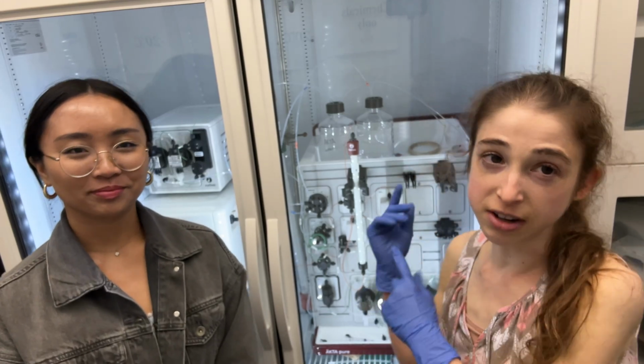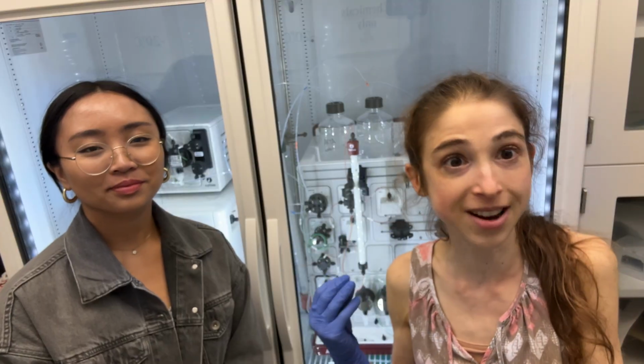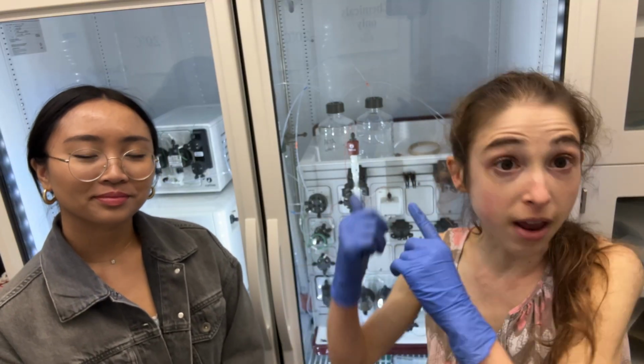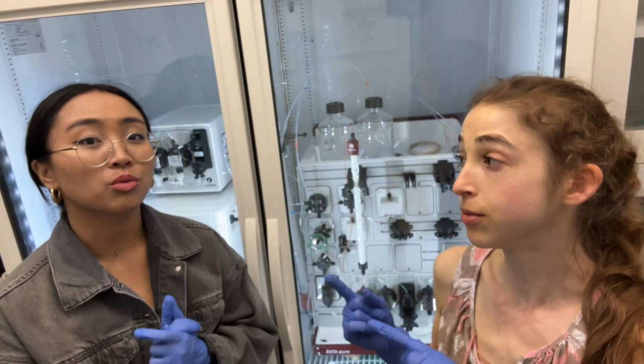If you're not going to be using a chromatography column for more than a couple days, you're going to want to store it typically in 20% ethanol to keep things from growing, because things have a tendency to grow in these columns and we don't want that to happen. So we're going to run ethanol through our column, but before we run ethanol through our column, what are we going to do? We have to wash it with water.